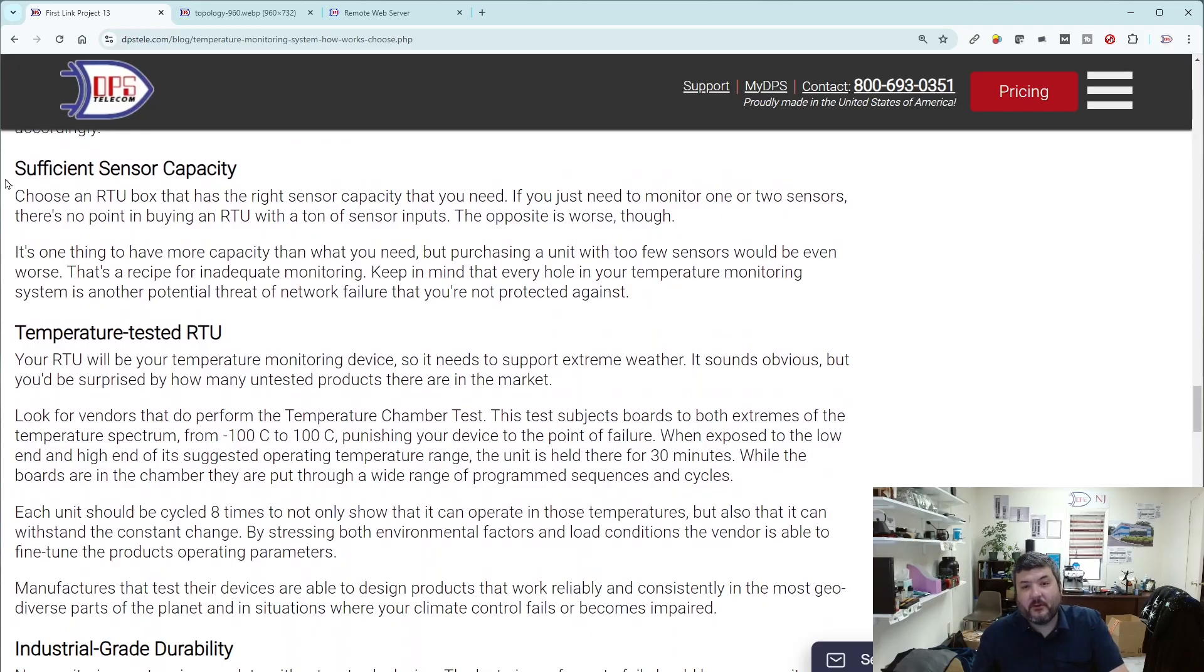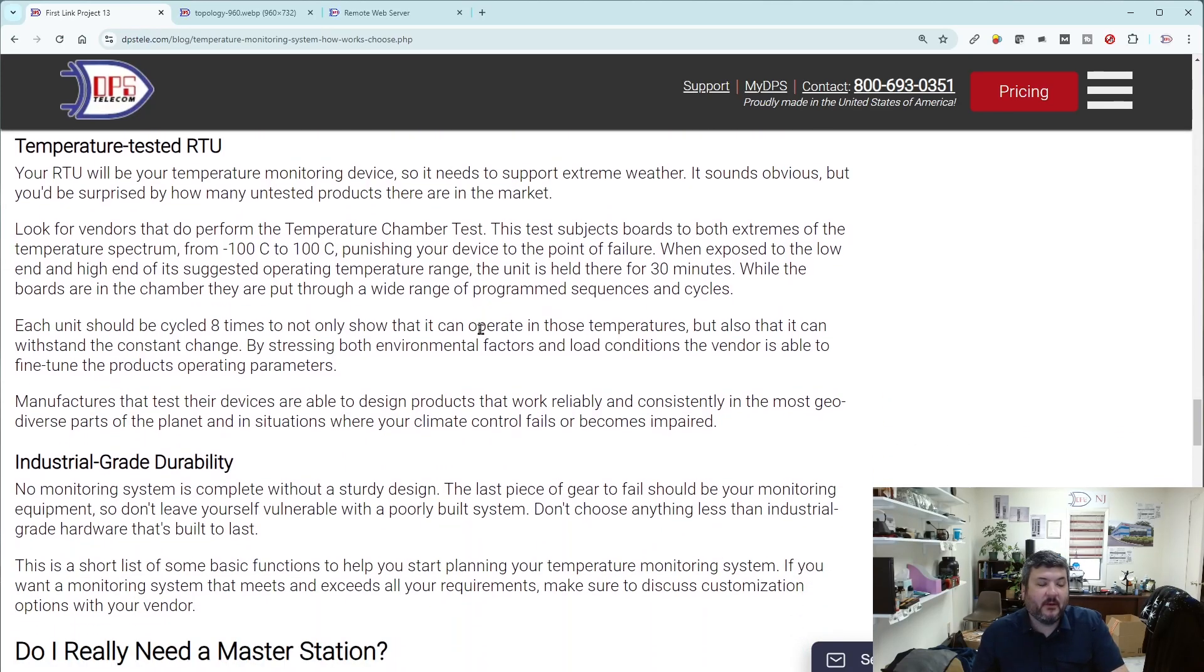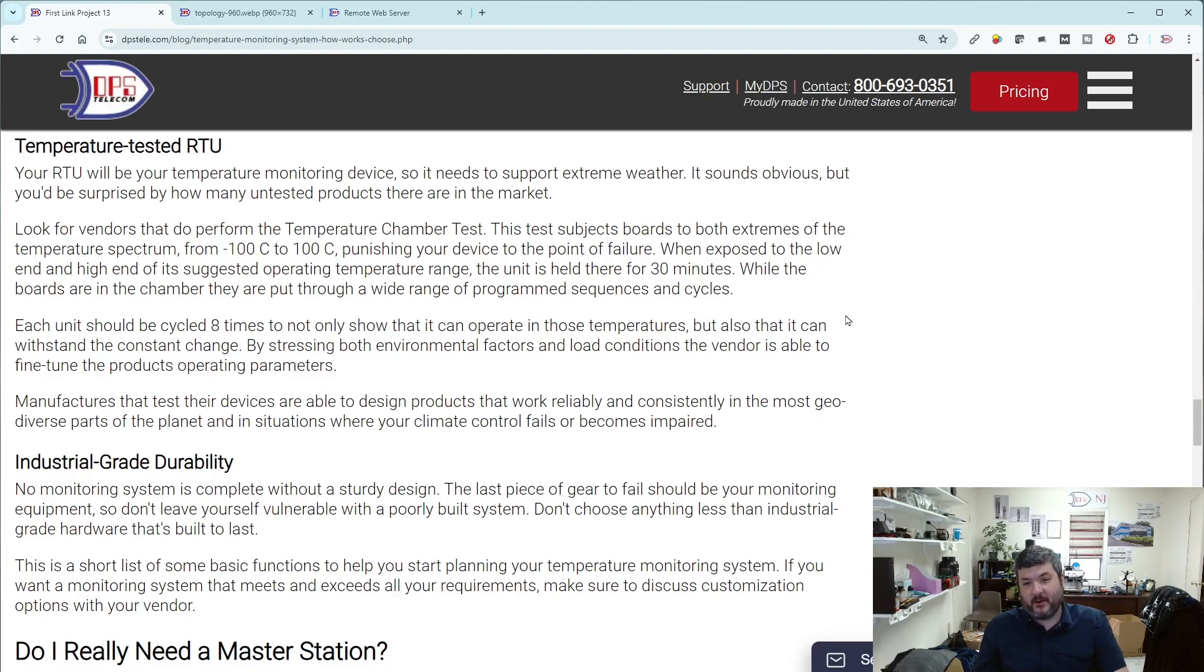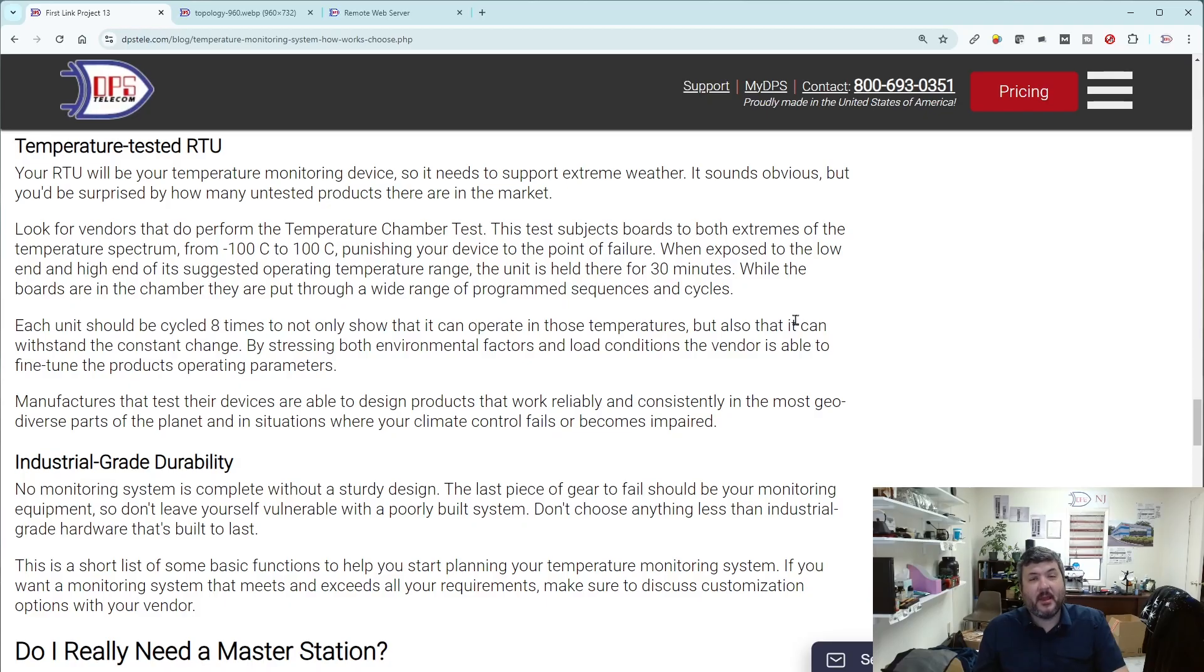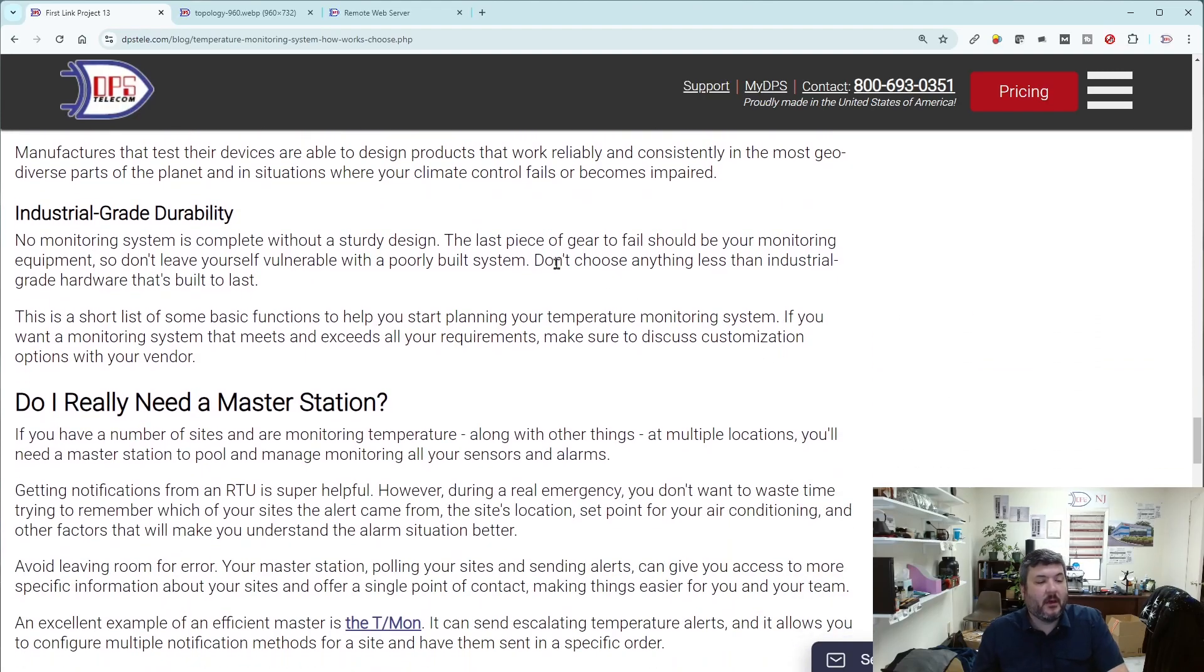Make sure the RTU can hold as many sensors as you need. If you want to monitor temperature in six different places in a building, be sure the RTU can support that many sensors. As we're talking about monitoring temperature, we build at DPS two different temperature ranges for our remotes. Our standard range is roughly a little below freezing to about 132 Fahrenheit. The wider range can be all the way up to 70 Celsius on the top end, and you can go down to about minus 40, which is actually the same in both Fahrenheit and Celsius. That speaks to more broadly industrial grade durability.